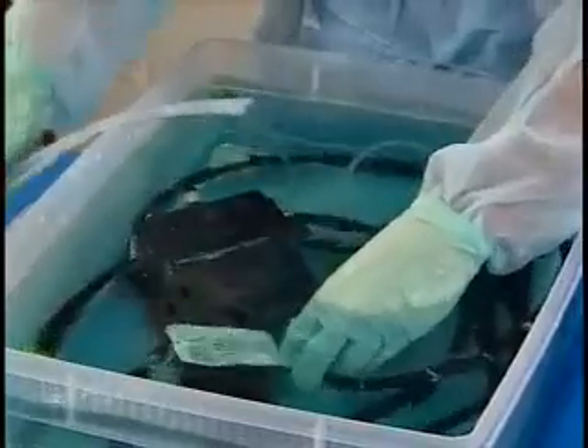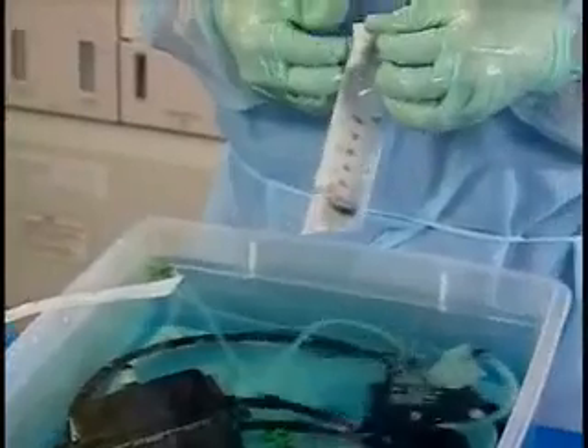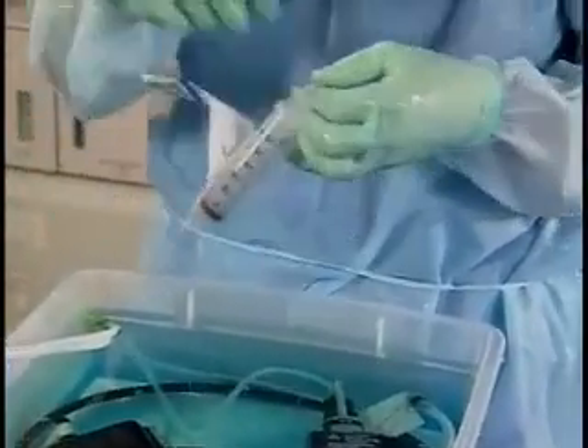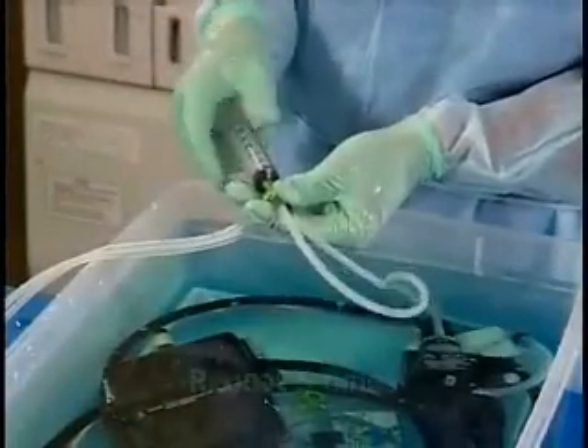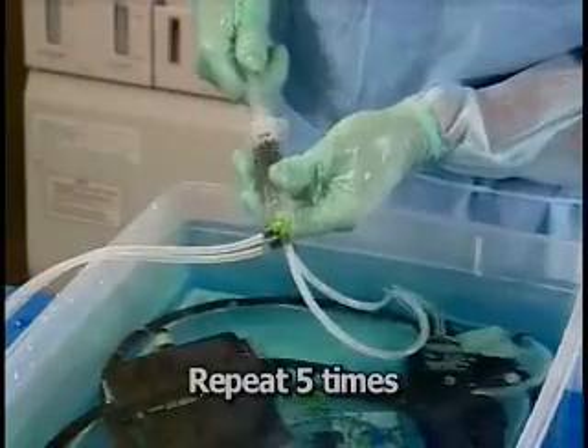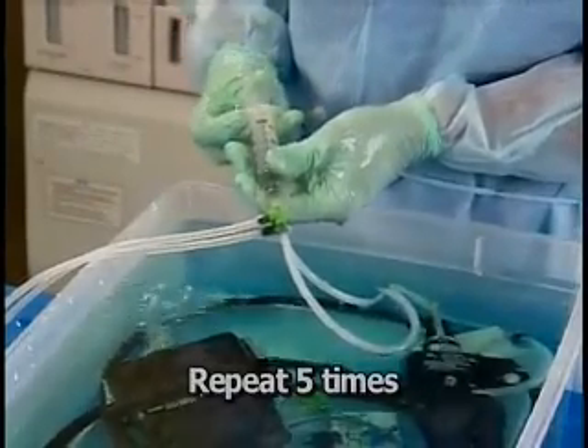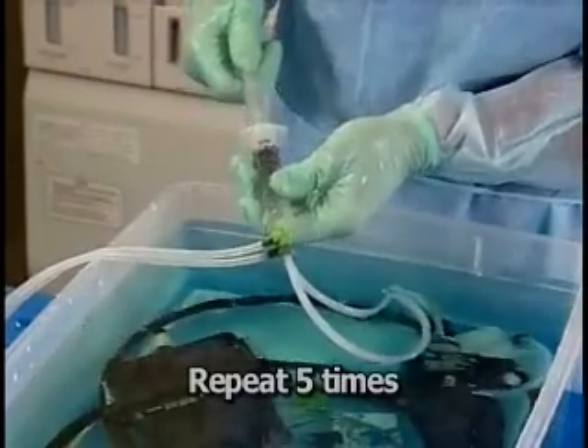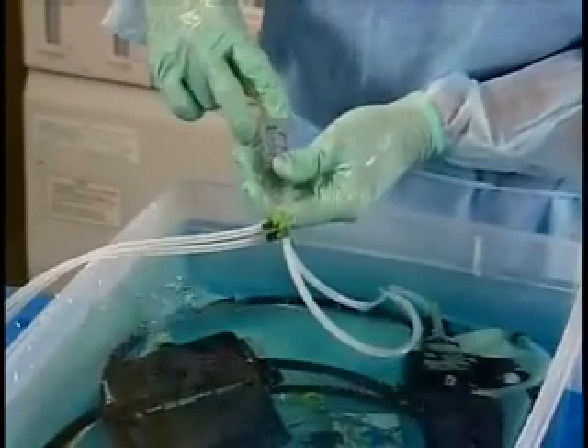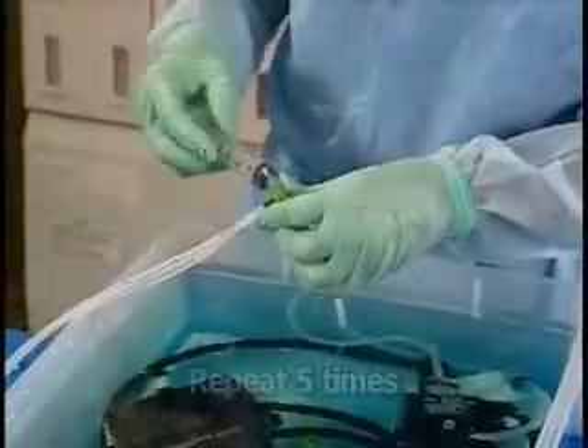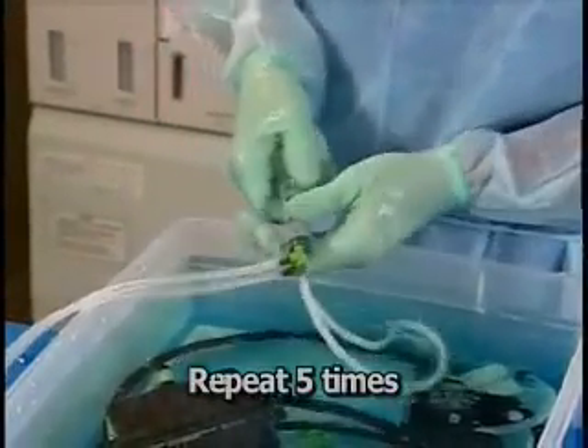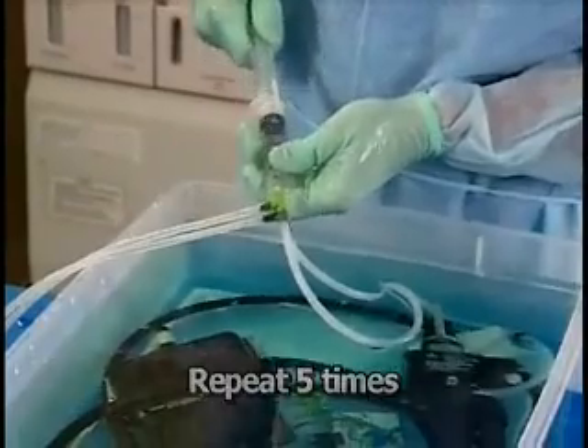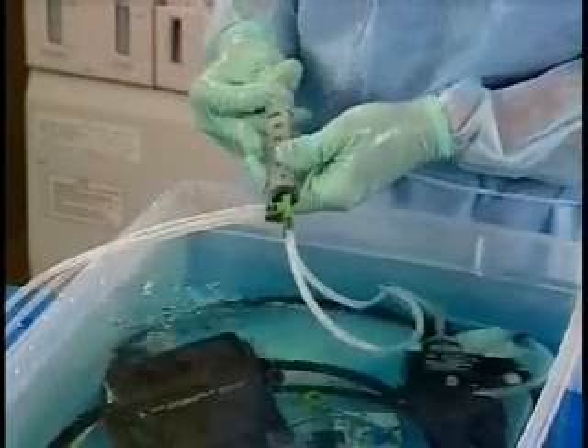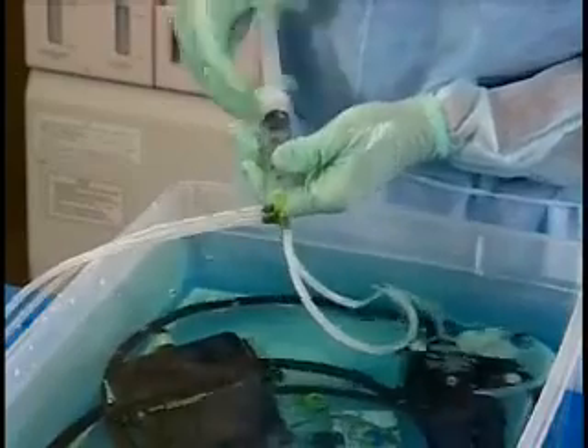Remove the intake filter from the disinfectant solution so that it will draw up air. Connect a sterile syringe to the air-water channel port and pump at least 5 times to expel the disinfectant from the air, water, and balloon channels. Move the syringe to the suction port and pump at least 5 times to expel disinfectant from the suction channels. At the end of the process, you should observe air bubbles exiting the channel openings.